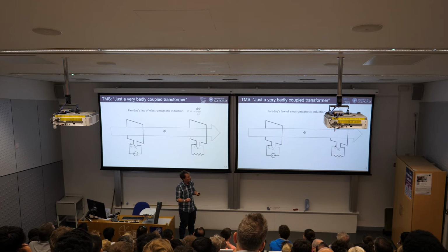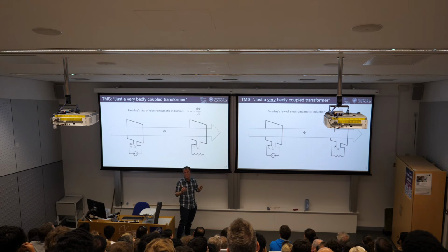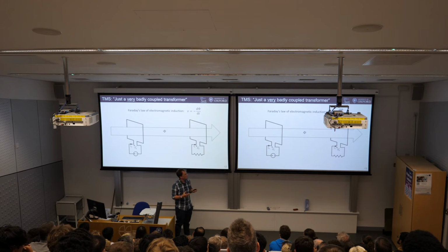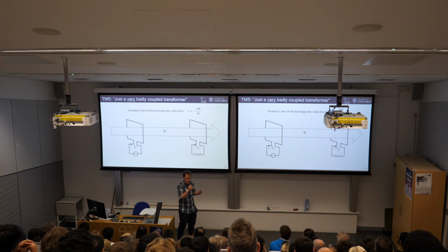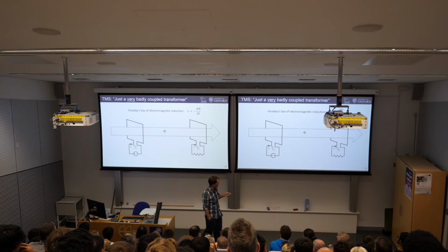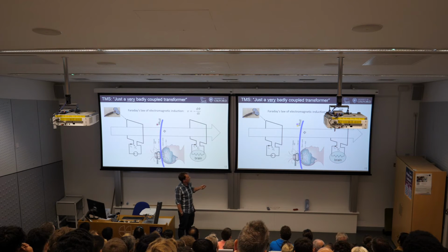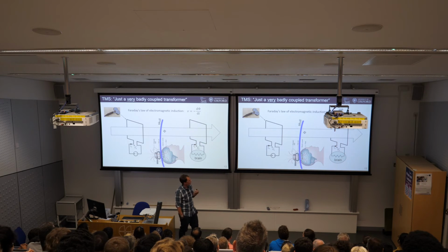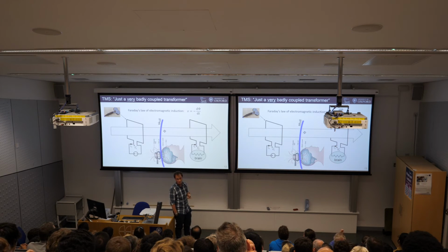It's a transformer, and that voltage in the brain is going to cause a current to flow in the brain, and that current is going to modify the behavior of the brain, either suppress or activate neurons and have a medical effect, okay? Which maybe we'll come on to a bit later, talking about the engineering here rather than the medicine. So that's the coil. The magnetic field passes through the skull, pretty important part of the deal, and then the brain is the receiving coil, if you like. I'm going to try and show you how we can use some of the theory we've just seen and model this system.